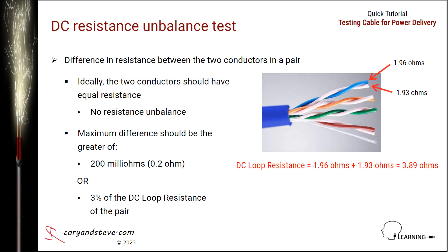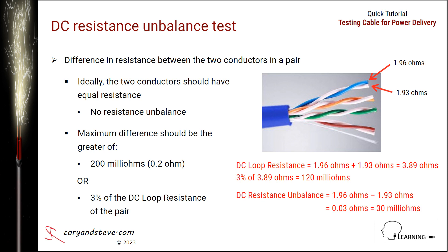In the example shown, 3% of the 3.89 ohm DC loop resistance is 120 milliohms. So the pair passes the test with 30 milliohms, which is lower than the maximum allowable 200 milliohms.